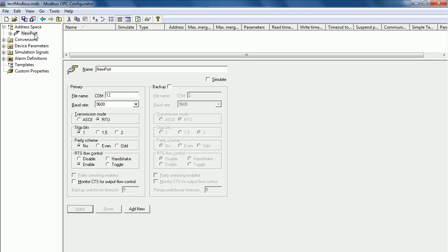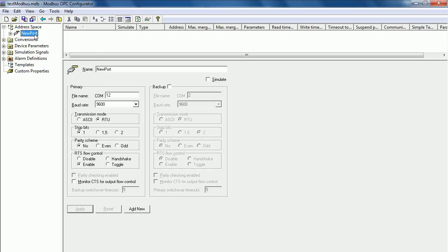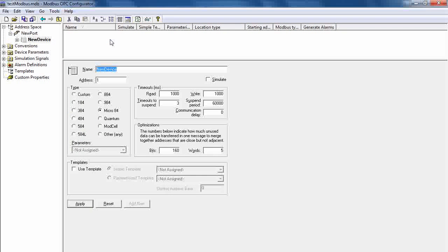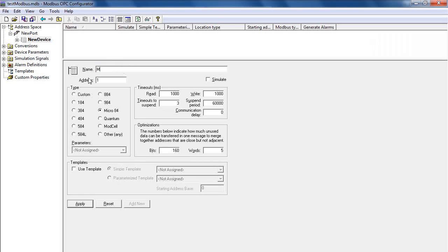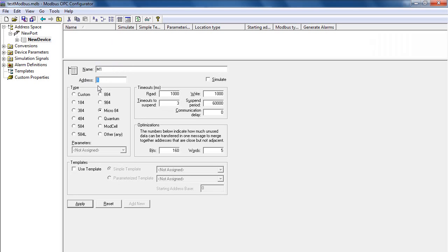Now right click on the port that we have created and select New Device. For Modbus, specify the name of the device. You have to specify the Modbus address of the device that you would like to connect to. In this example, I connect to Modbus address 1.